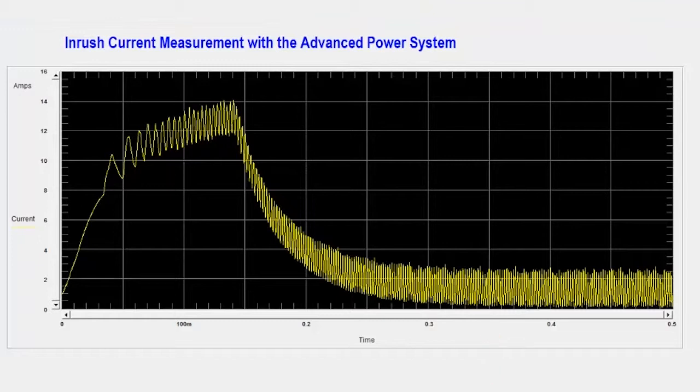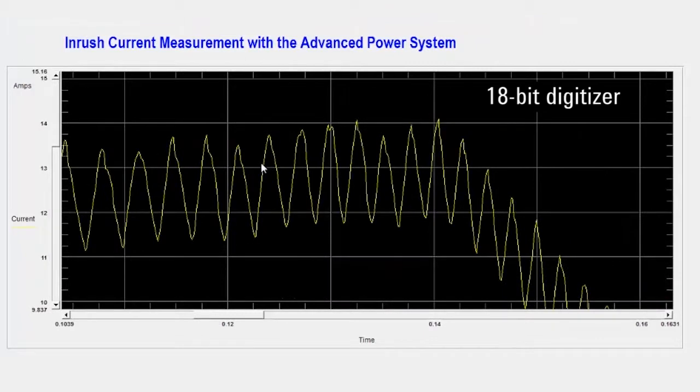Now the great thing about capturing this with the APS is we have an 18-bit digitizer. We get extremely high resolution so we can easily zoom in on any part of this current profile. Let's zoom in on the peak. Once again, 18 bits of resolution and we have a digitizer that can run at 200,000 samples per second.